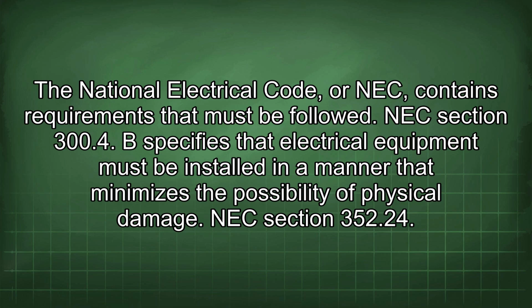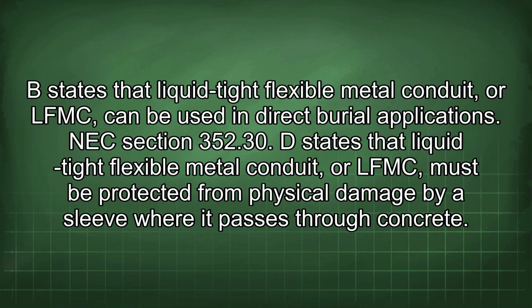NEC Section 300.4 B specifies that electrical equipment must be installed in a manner that minimizes the possibility of physical damage. NEC Section 352.24 B states that liquid tight flexible metal conduit, or LFMC, can be used in direct burial applications. NEC Section 352.30 D states that LFMC must be protected from physical damage by a sleeve where it passes through concrete.